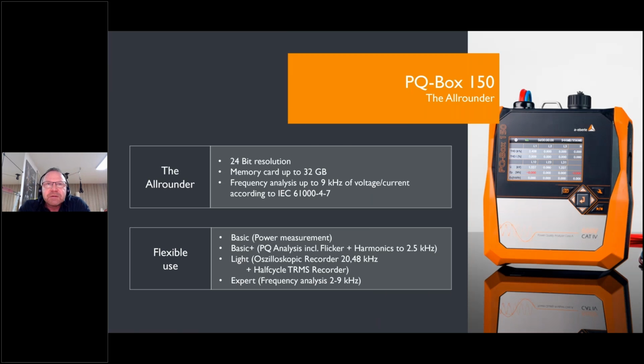The all-rounder is the PQ-Box 150, and here we sell most of the pieces. The big difference to the PQ-Box 50 is a higher resolution. In this device, we always use 24-bit resolution, so it's much more than the 16-bit of the PQ-Box 50. And we measure the new range for supraharmonics from 2 to 9 kilohertz, which is also not possible for the PQ-Box 50.